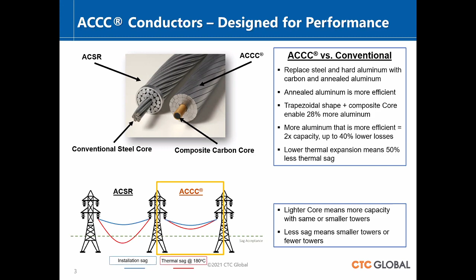So why does a utility take a look at this advanced conductor? What we see generally are 3 reasons. First off, their standard conductor, what they've always been using, just doesn't work for one reason or another. The sag, they can't get the right clearance. Ice load is too heavy. The right-of-way is narrow, and they need to upgrade the power line down that right-of-way, and they just can't do it with their standard conductor. Those are some reasons why they may consider it, so what other choice do I have?